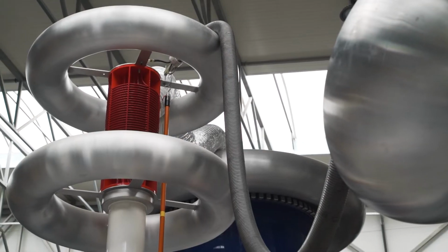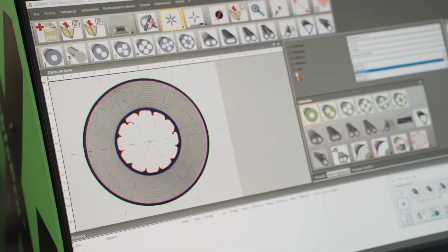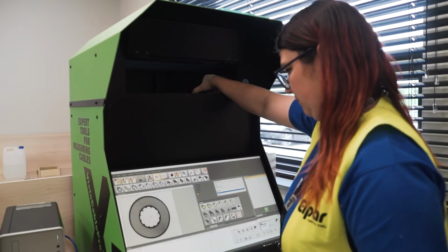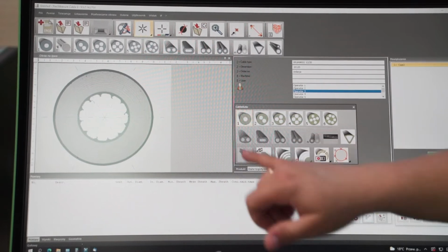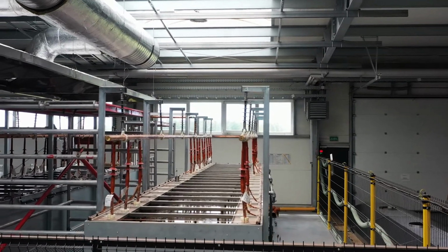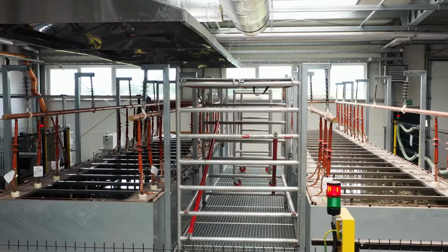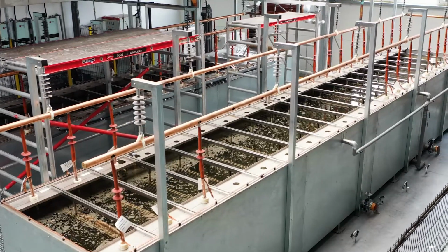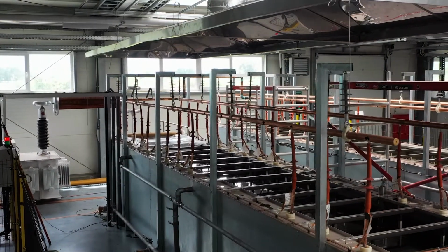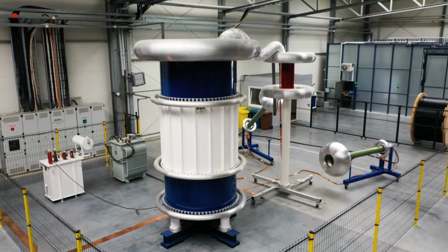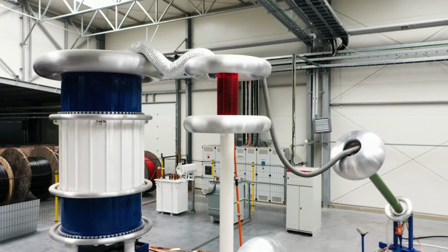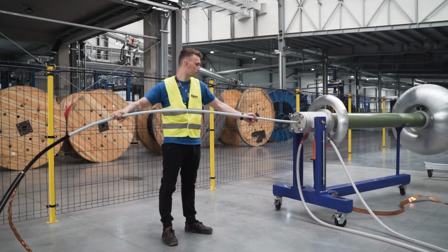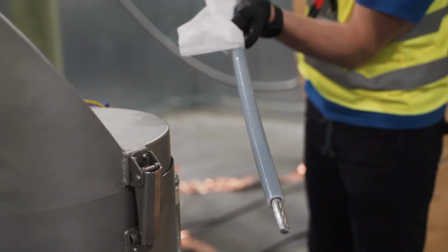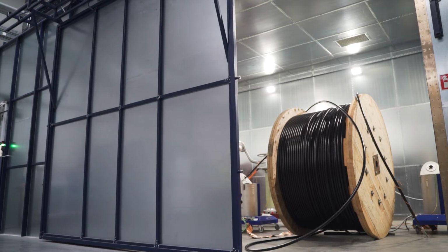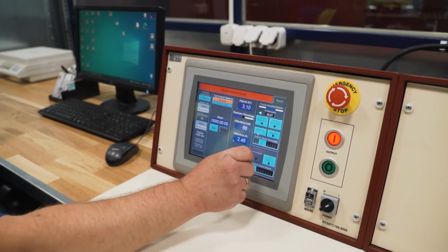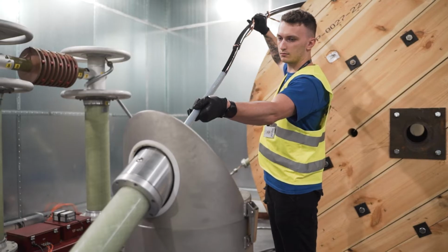All products undergo rigorous quality tests in terms of their electrical, constructional, mechanical, and physico-chemical properties. Long-term testing of insulation systems involves immersing cables in water at a temperature of 40 degrees centigrade, to which a voltage of 36 kilovolts is applied. Half the samples are removed from the water after 1 year, and the other half after 2 years. Now it's time for a breakdown voltage step test using the special voltage system to apply voltages as high as 450 kilovolts. In addition, the cables are subjected to electrical measurements in a Faraday cage.